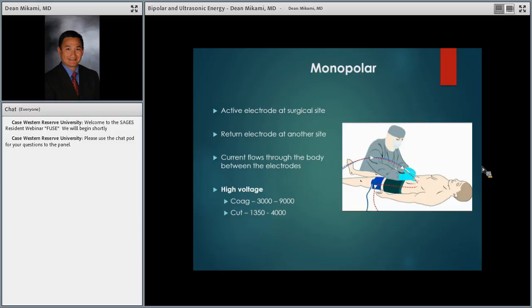You also have, in the old terms, the grounding pad, but we don't call that the grounding pad either. We call it the return electrode. So basically what happens is the current wants to go from the active electrode at the surgical site where you're working, and it wants to complete the circuit. That's what you need to understand in monopolar energy used for surgery. Your ESU, or electrosurgical unit, wants to complete the circuit. It's not really looking for ground, it's looking to complete the circuit. So the active electrode is in your hand, your active electrode pencil, and the return electrode is on another site.